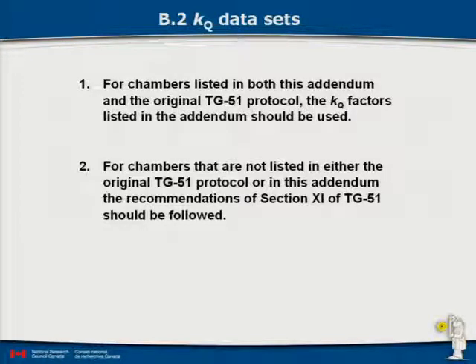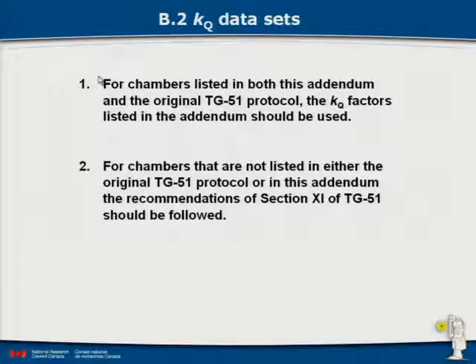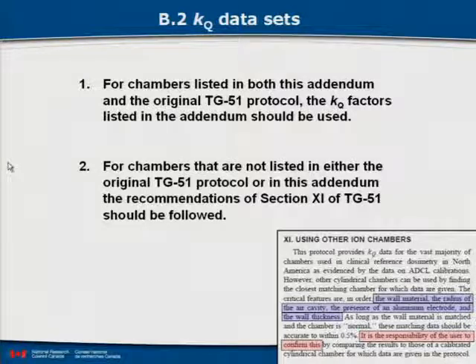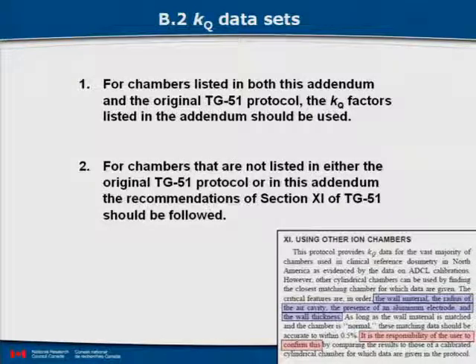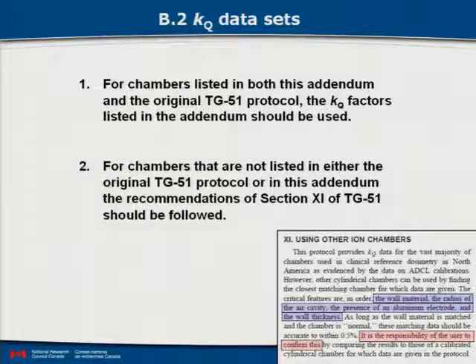Moving on to KQ data sets: TG51 is still valid, but there'll be an addendum with KQ data. The recommendation is that if there's KQ data in the new addendum for your chamber, you should use that data. If you have a chamber not listed in the new addendum or the original document, there is a section in TG51 on how to obtain a KQ data set from those published in the protocol. Importantly, you can't just look it up and pick data — you have to confirm your choice by comparison with a listed chamber. The shorthand is: get a chamber that's listed.